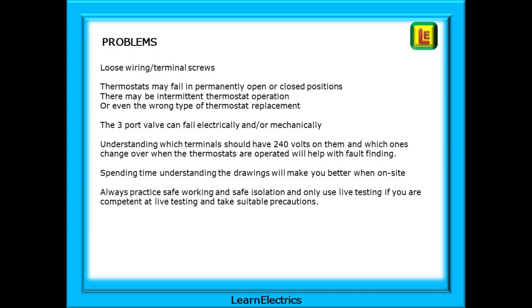What are some of the problems that might be encountered? Loose wiring or terminal screws, especially after maintenance work. Thermostats may fail in the permanently open or closed positions, or just be intermittent in operation. Or the wrong type of thermostat replacement might have been fitted. And the three port valve can fail electrically and/or mechanically. Understanding which terminals should have 240 volts on them and which ones change over when the thermostats are operated will help with fault finding. Always practice safe working and safe isolation, and only use live testing if you are competent at live testing and take suitable precautions.